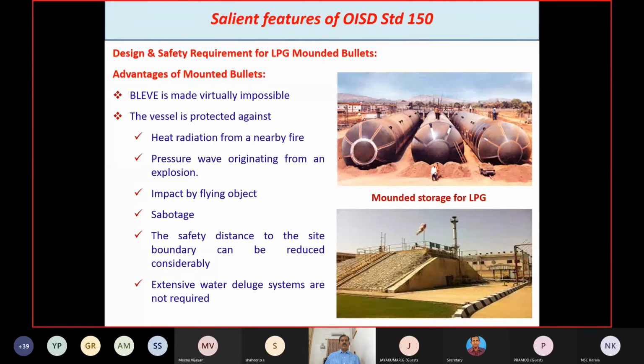If you go for spheres, the distance should be maintained. For mounded bullets, space constraint is not an issue, as you need not maintain a larger distance. Similarly, a water sprinkler system or extensive water deluge system is not required for mounded bullets. This system is required only for the exposed area, manually, and only on that decision do we need the deluge and sprinkler system.